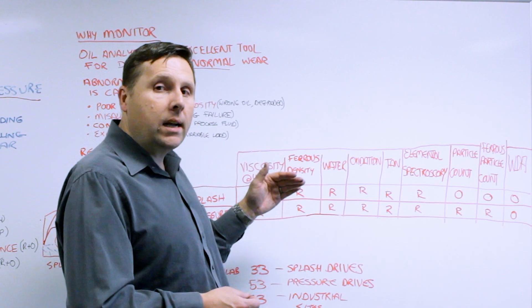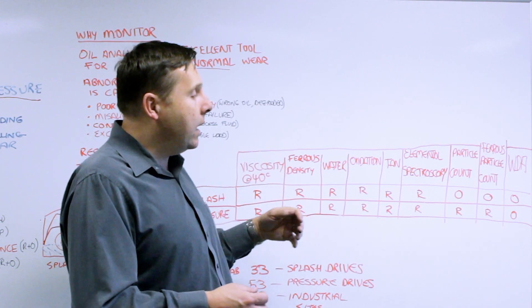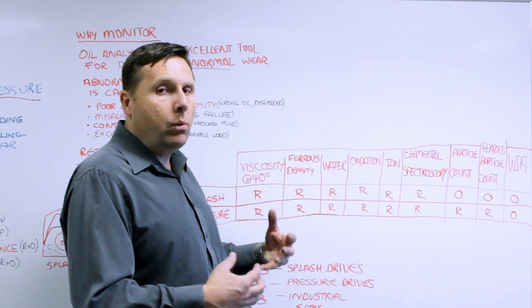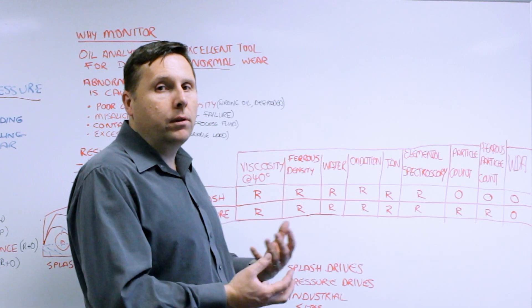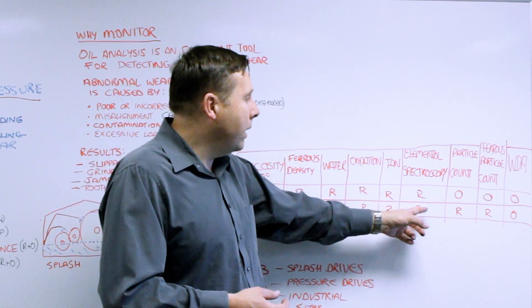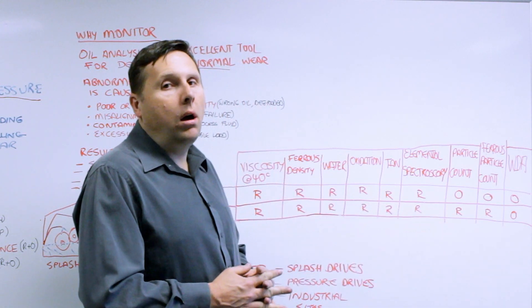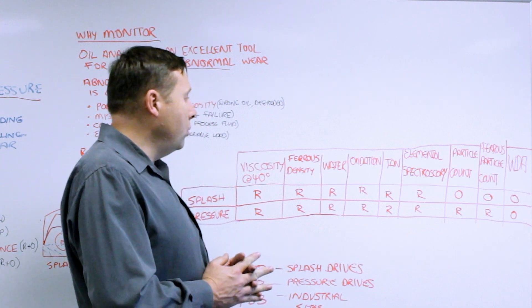But if you have pressure lubricated systems the viscosity is much lower and it's usually filtered because it's needed for filtration for the pump so therefore we recommend particle count on a pressure lubricated system.